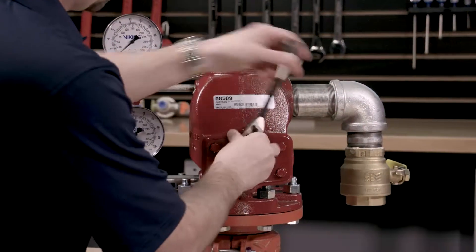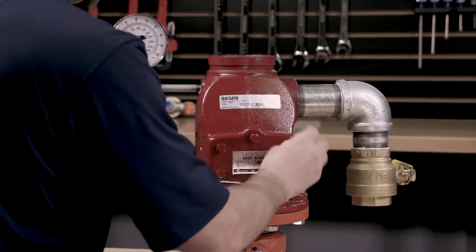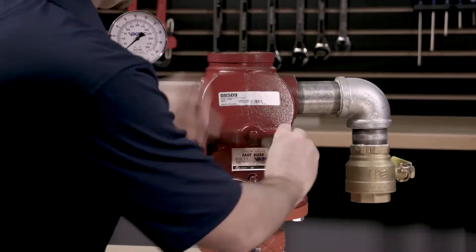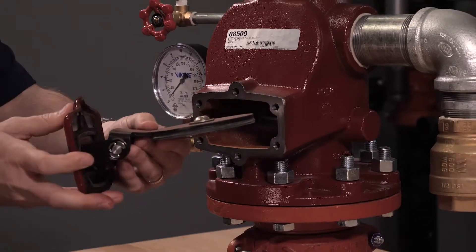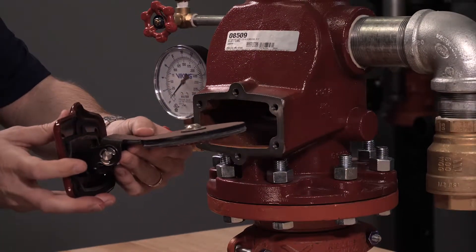To replace the clapper assembly we will first need to remove the cover screws from the cover of the valve. The clapper assembly is connected to the cover of the valve and the components will be removed simultaneously.